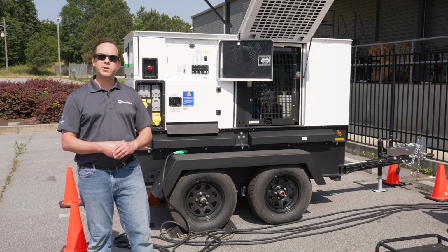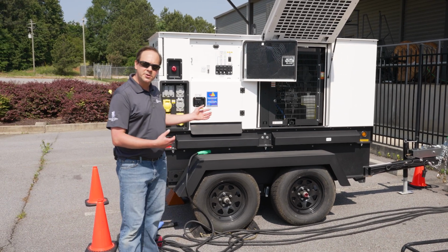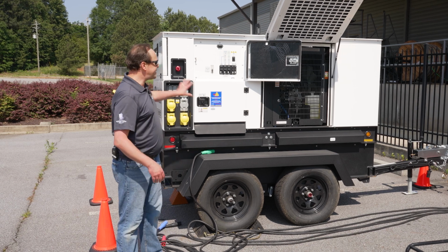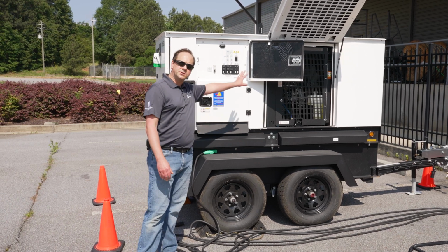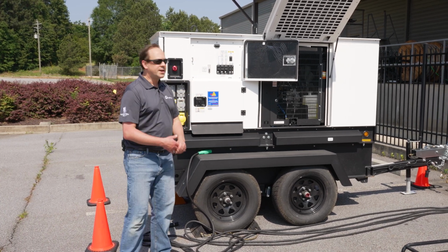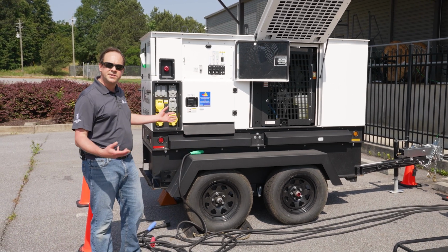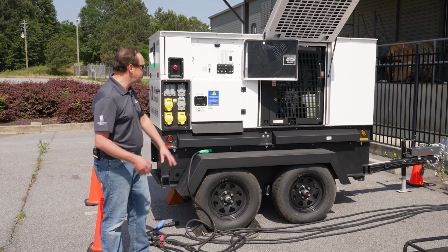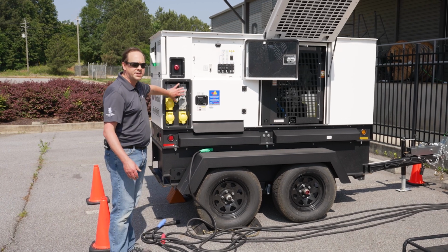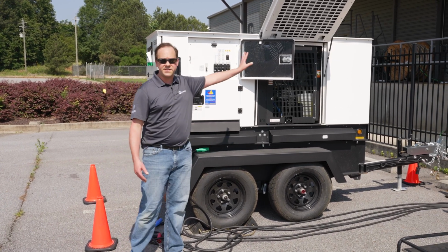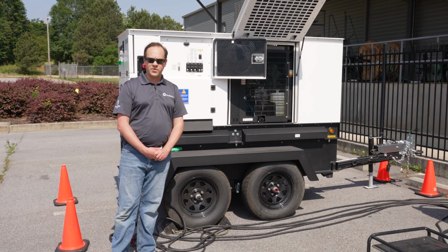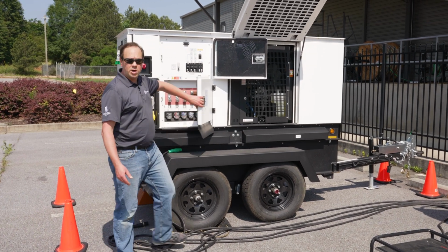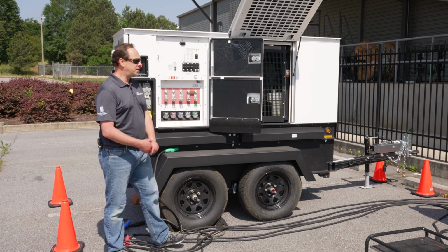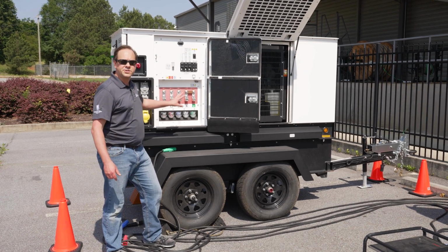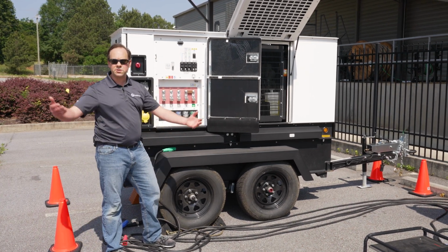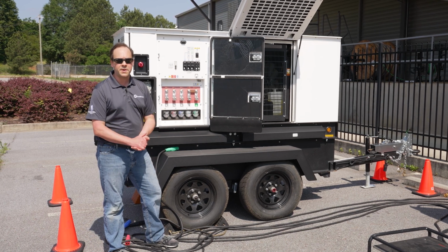Now, in any situation, what you usually have is a temporary generator or a temporary power pole that has a connection point that's larger than what the receptacles are able to do. In this generator, if you're trying to get 200 or 300 amps out of it, you're not going to be able to do it using the receptacles here, or if you did, they'd be all over the front of this thing. So in most cases, you're going to find either what are called cam lock connectors, or you're going to find a lug where you can connect that higher amperage service to enable you to bring service to those higher amperage boxes and distribute the power down.